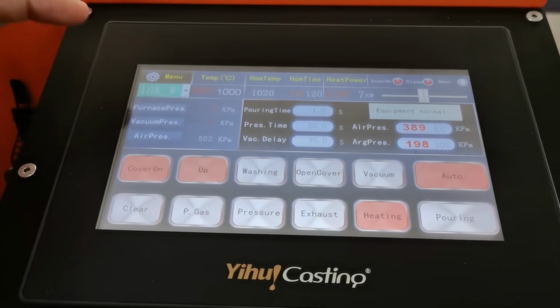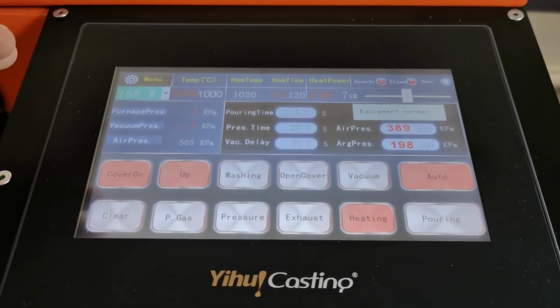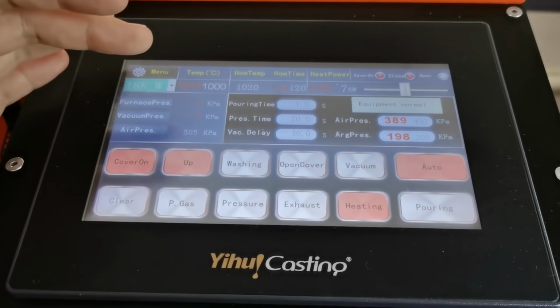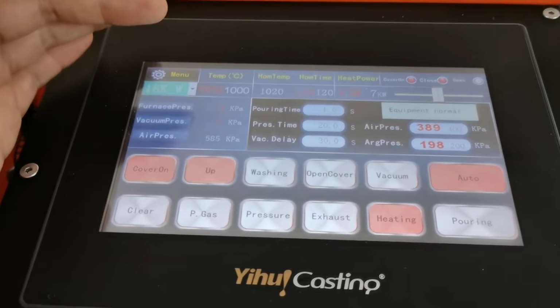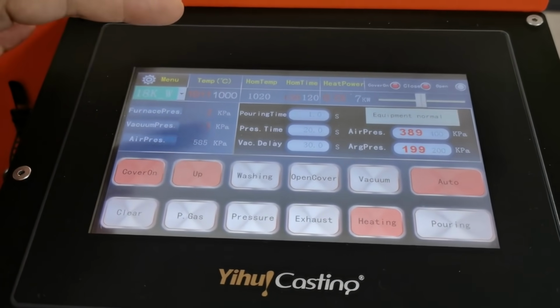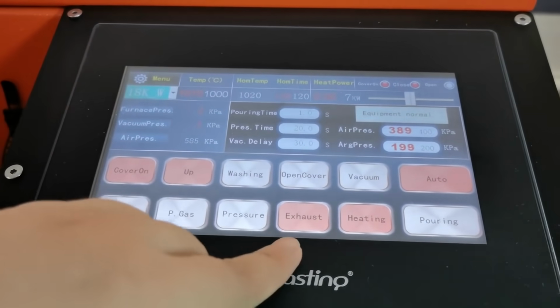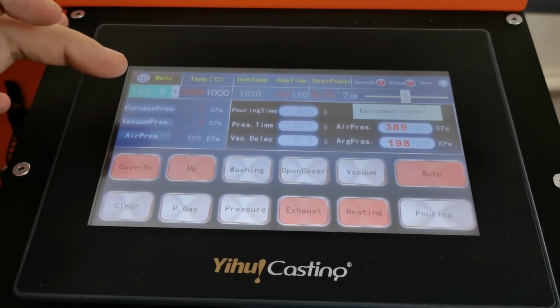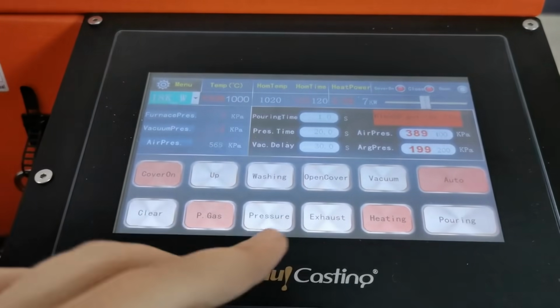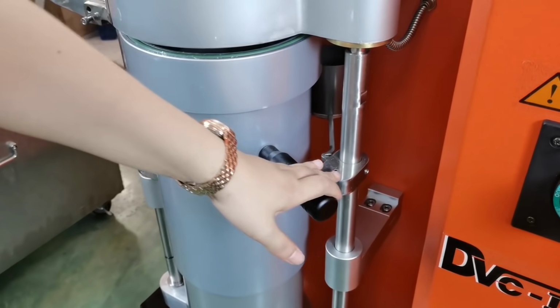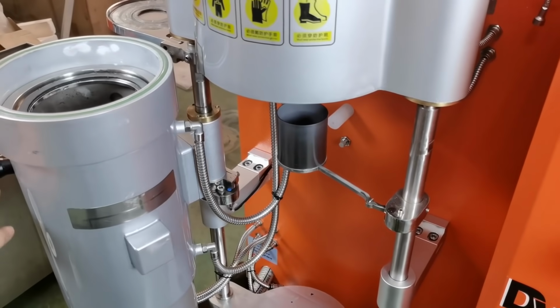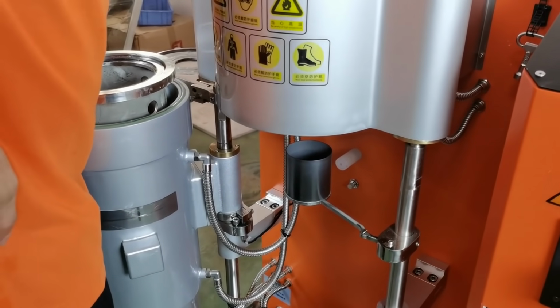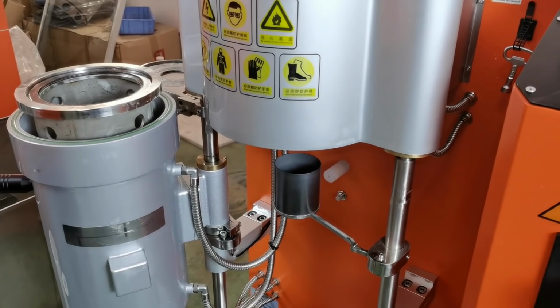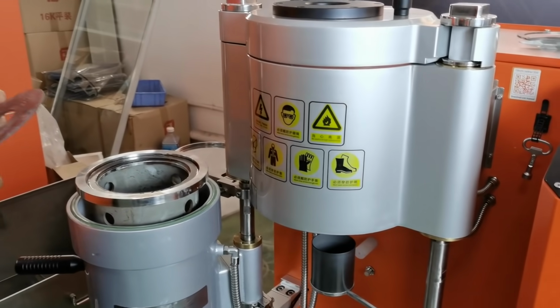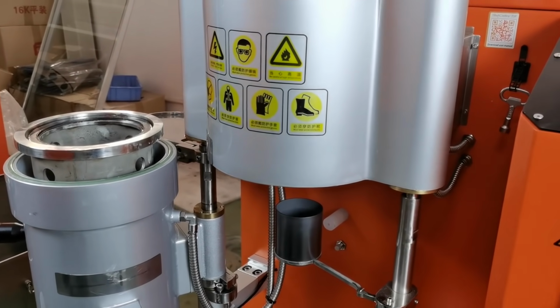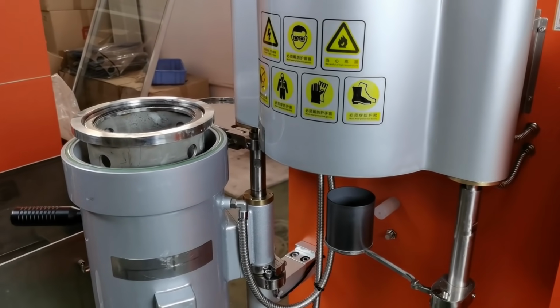Now homogenization finished. Then the temperature will drop down to the casting temperature. But it need not be exactly 1000 degrees. According to our design, when it reaches 10 degrees close to the preset temperature, the system will start exhaust. We can see here, exhaust. Once we see here the pressure becomes normal atmospheric pressure, then the down chamber moves up automatically. Then we push the down chamber back to the left. Then we can load the flask. Okay, we're waiting for our engineer to load the flask into the down chamber. It's coming.